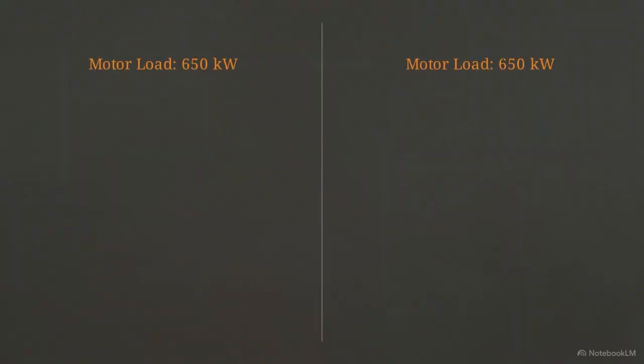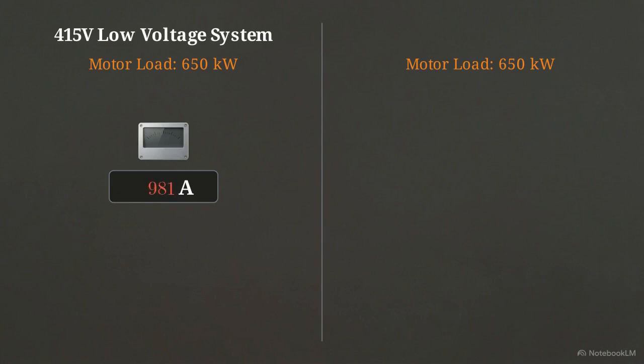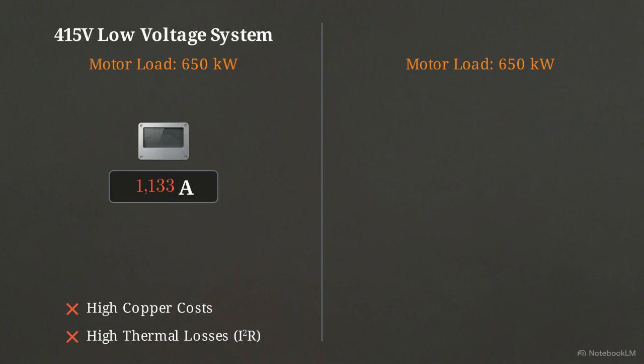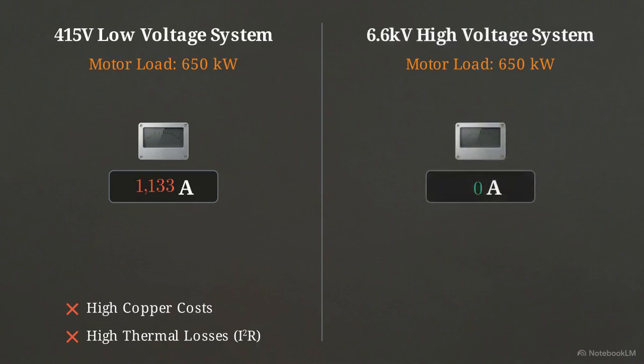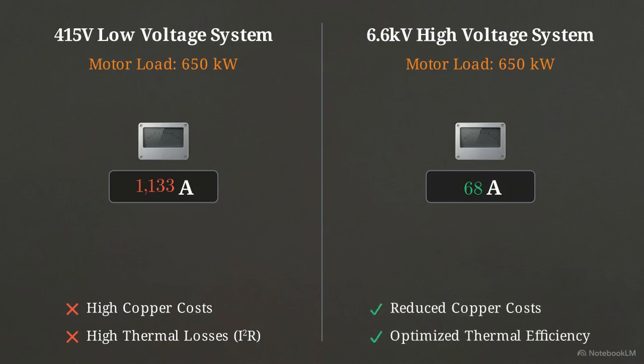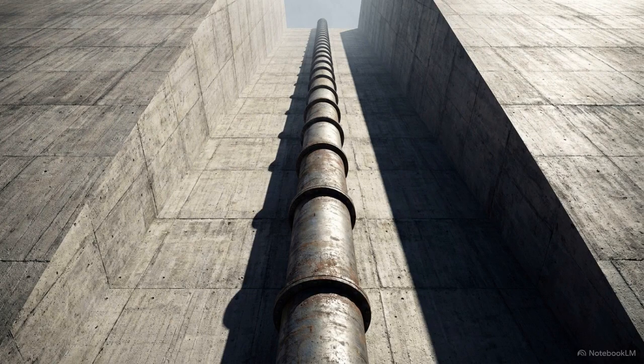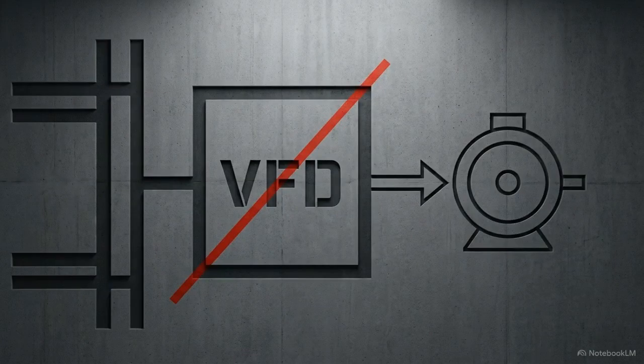This numerical breakdown illustrates why these motors operate at high voltage. At 415 volts, a 650 kilowatt motor pulls over 1100 amps, necessitating impractically thick copper cables. Stepping the voltage up to 6.6 kilovolts drops current to 68 amps, slashing copper costs and thermal losses. Because the vertical turbines must overcome a 202.5-meter static head, they need to spin at full RPM immediately. This eliminates the need for variable frequency drives, which are typically used to control motor speeds.